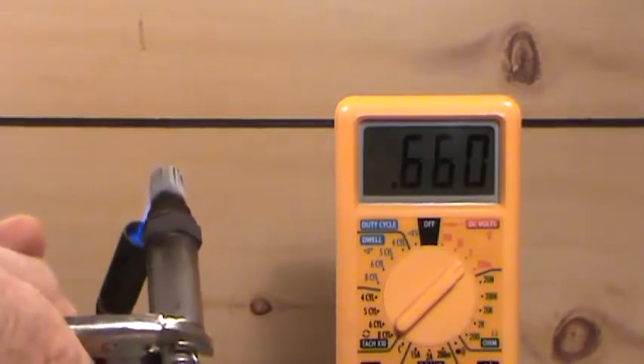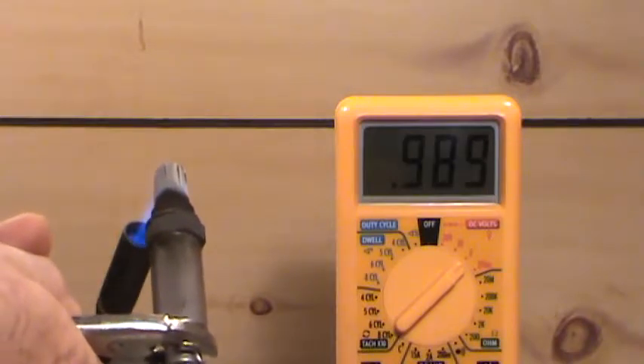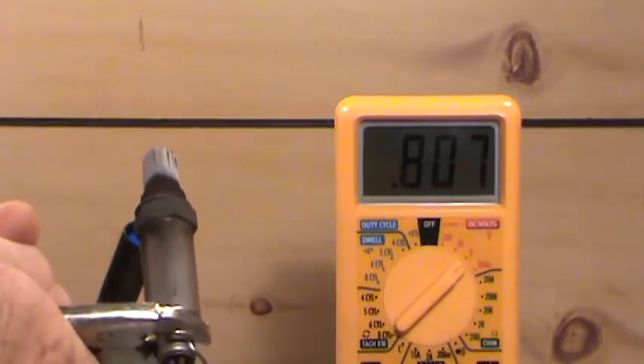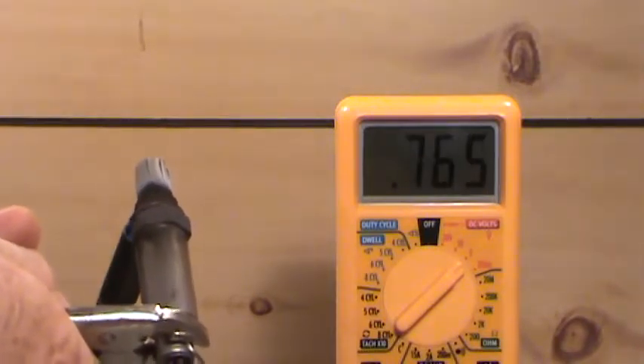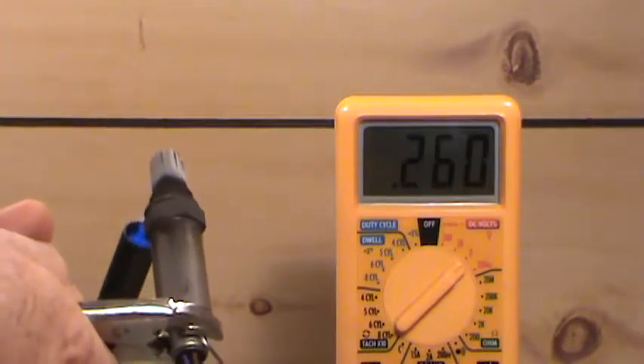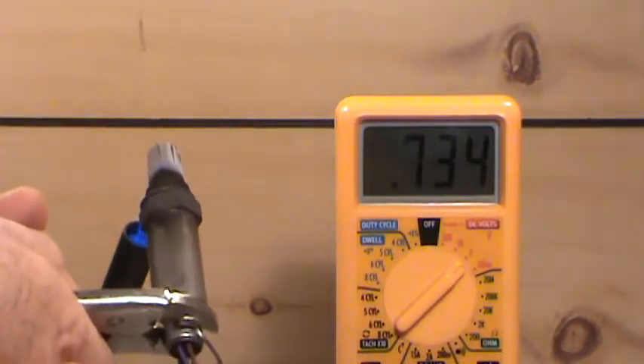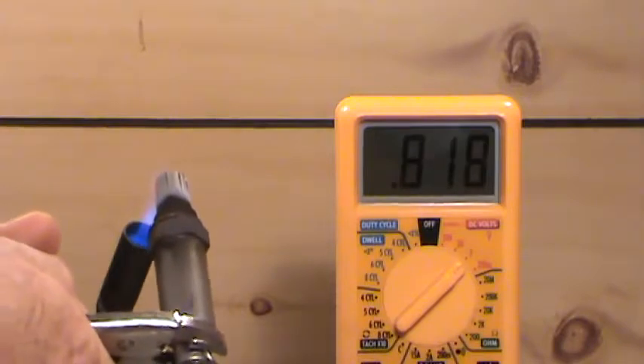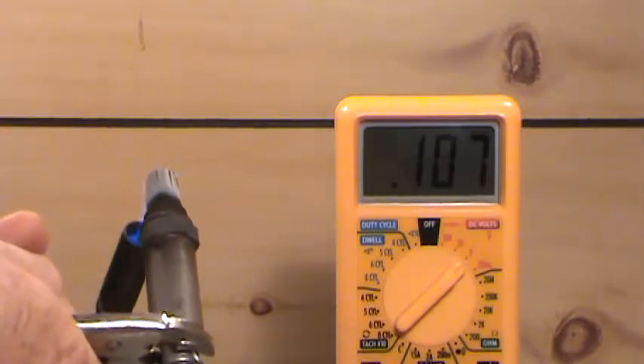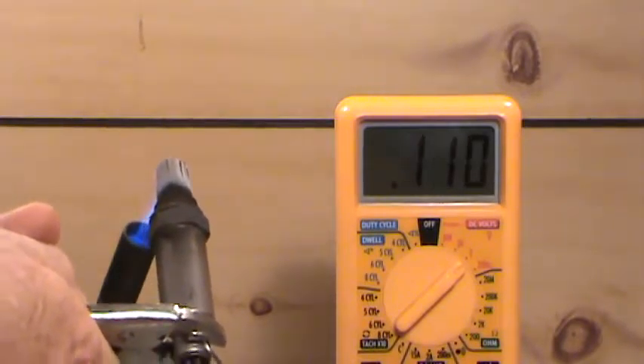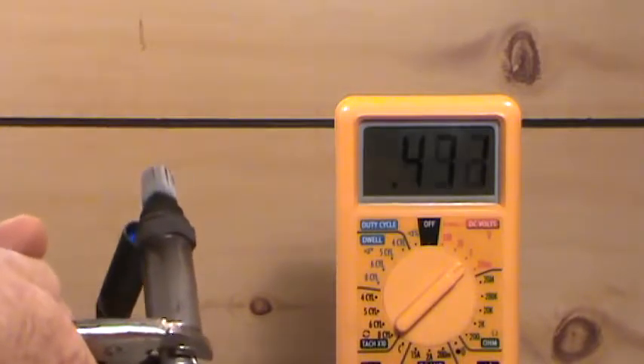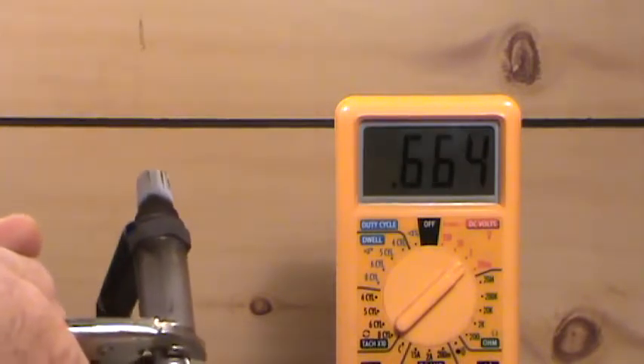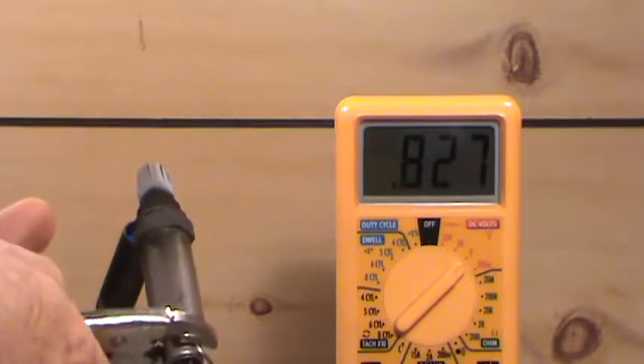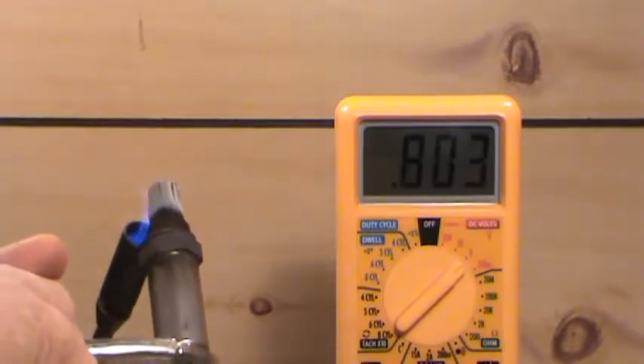So as you can see those numbers there, now for the final part of this test, I'll be taking the tip of this O2 sensor away from the flame, and those numbers should count down really quick, within under 5 seconds I'd say. If it goes down really slow, then you've got a faulty O2 sensor. Mind you, this one could still be contaminated with silicone or what have you, who knows. Anyways, watch the numbers, I'll try to get them up high and then see them fall off.